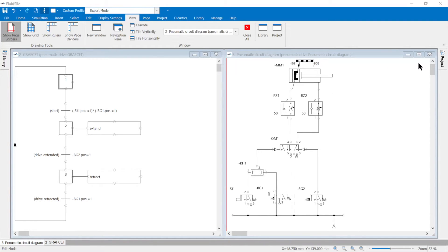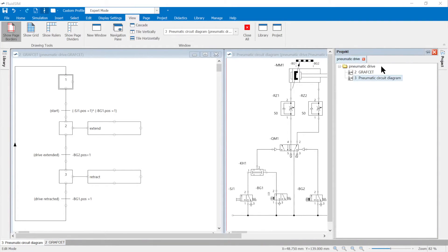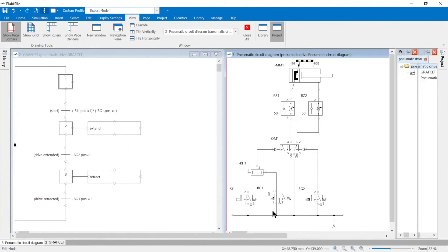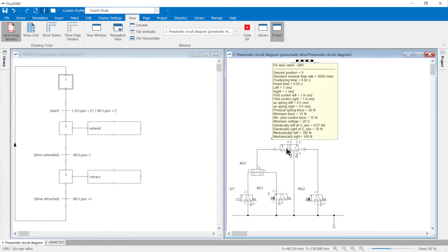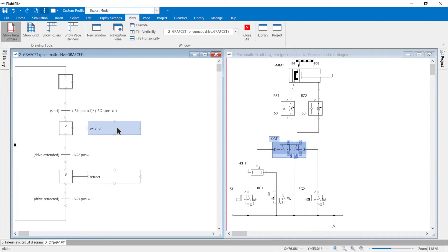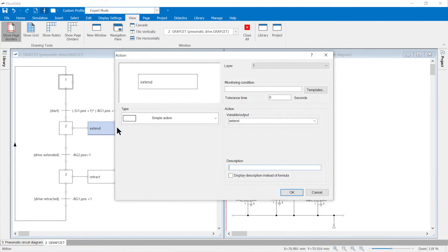Control of the drive with the GRAFCET: in graph control mode, the GRAFCET sequence can be simulated and the drive can be controlled with the GRAFCET. The MM1 drive can only be controlled indirectly in FluidSIM via the QM1 actuator. FluidSIM is a real-time simulation system that calculates the dynamics of the drives — a technology-neutral GRAFCET cannot be simulated in this way. The position of directional control valves can be controlled directly from a GRAFCET action using the POS set variable. The position values are 1, 2, 3, or 4.